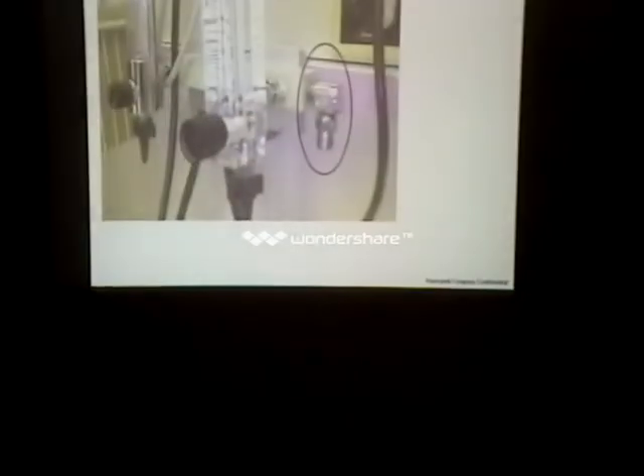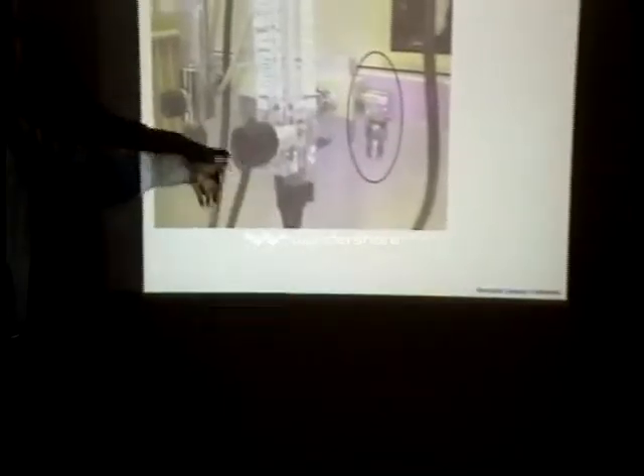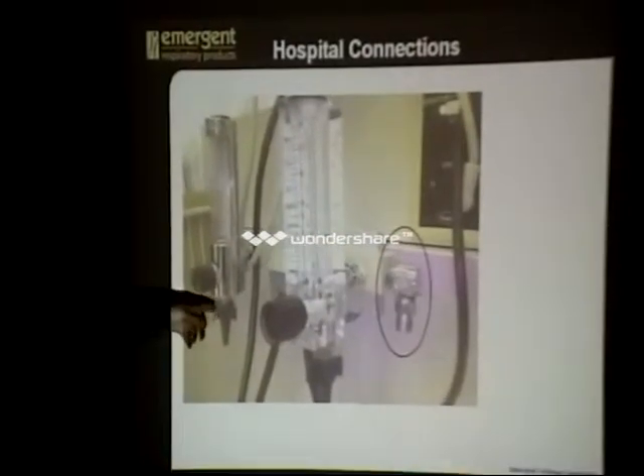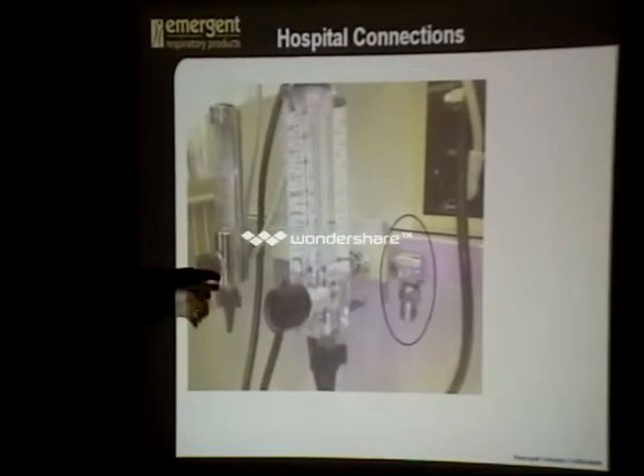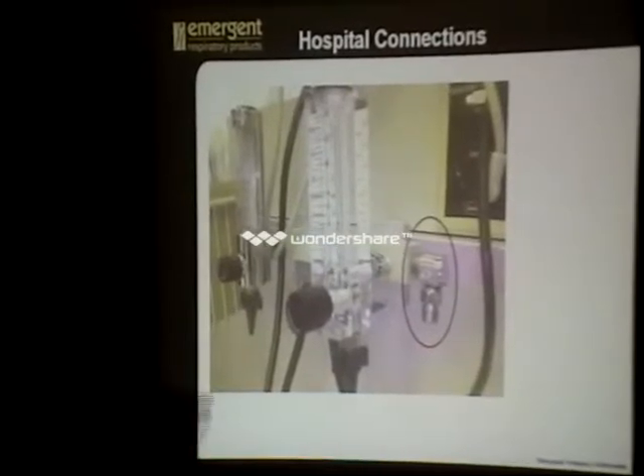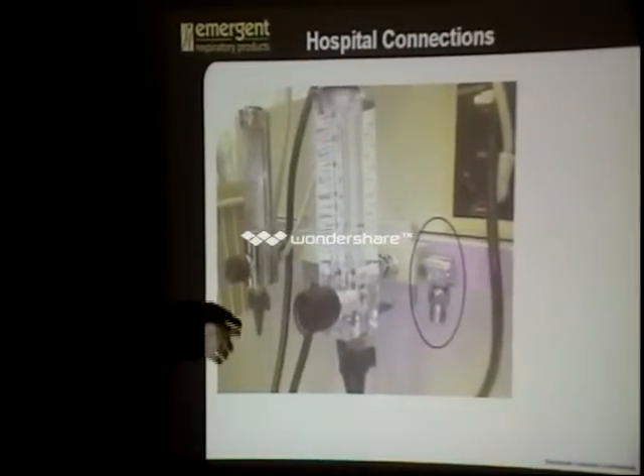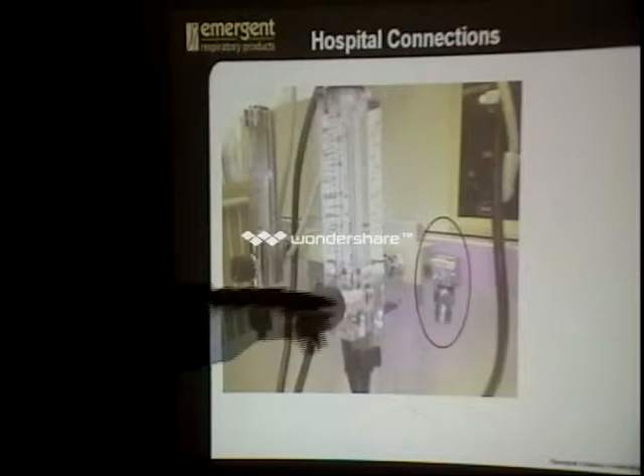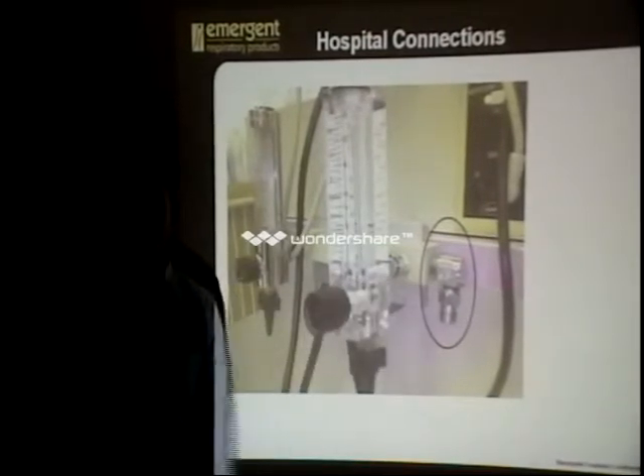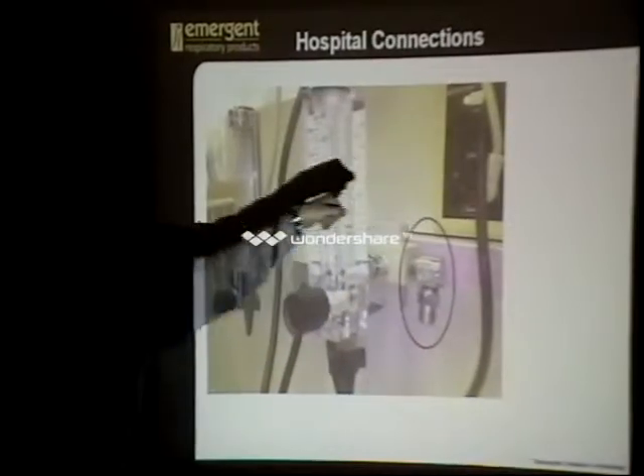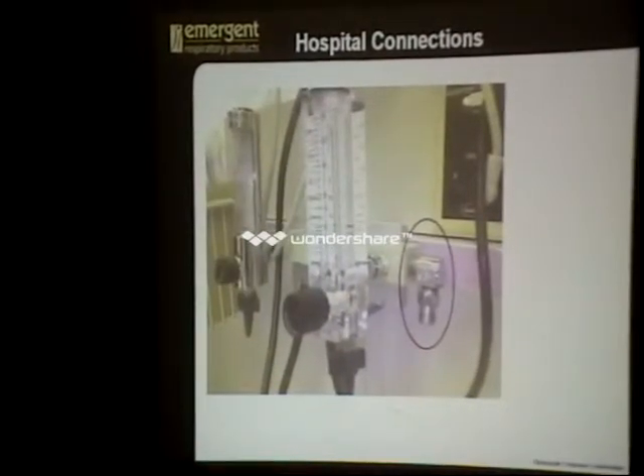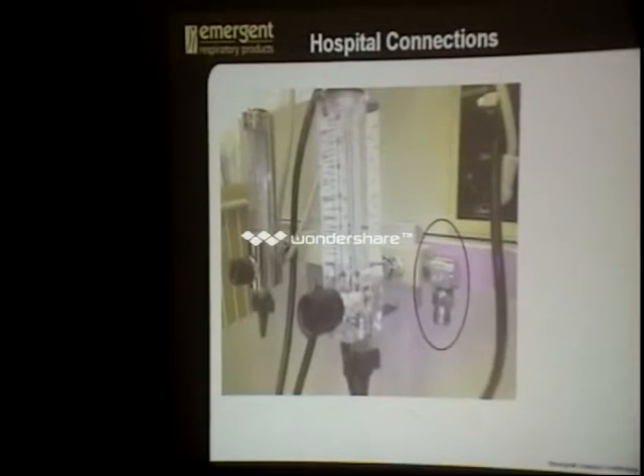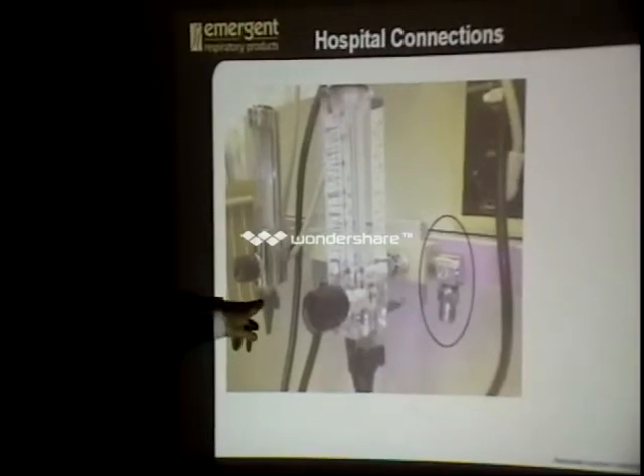Hospital connections. Grab that light switch for me real quick. This is a DISS port. However, off of these flow meters here, these Christmas trees will unscrew. If you unscrew the Christmas tree here, it will fit, but it will not be enough pressure to operate the unit. So make sure you're always going to the back off the high pressure ports. If you've got the quick connects, these Ohmedas actually, there'll be a wall line here, a green wall plate, and you can pop it into the wall plate and run it off the high pressure. Just make sure you're always going for the high pressure lines. Some EDs are different, but make sure you're not running it off the Christmas tree threads here.